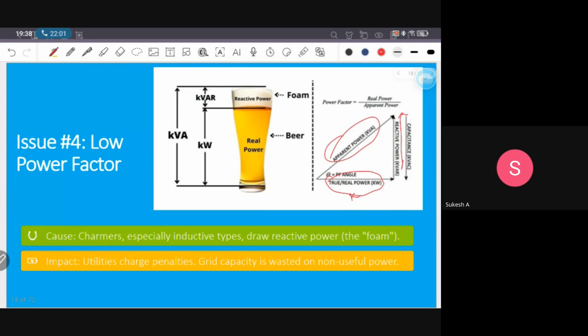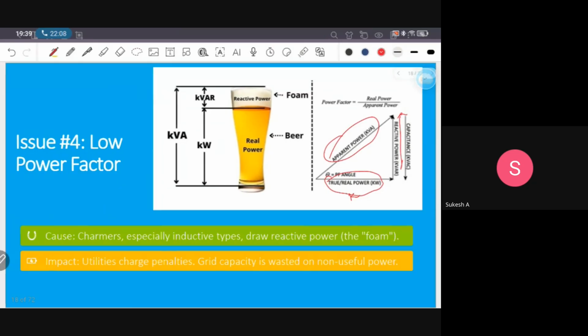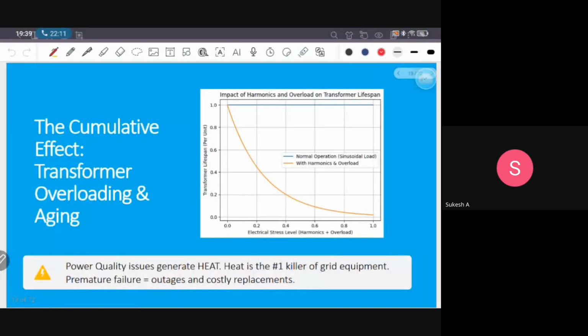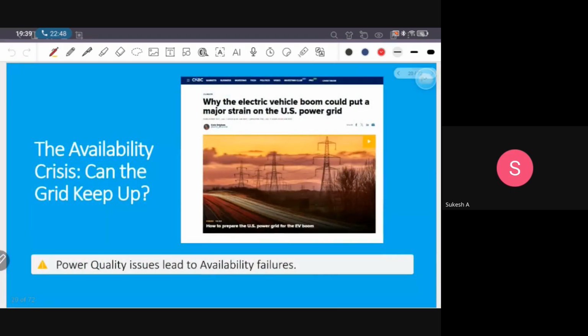And our EV loads and EV local loads are also drawing reactive power. So the cumulative effect is transformer overloading and aging. Here we can see the impact of harmonics on the transformer, and it is overloaded like this. So its lifespan is reduced like this. This graph is taken from, I forgot to add the reference. I will share the slides and add the references in them. It's a case study, and they plotted this graph smoothly showing lifespan reduction with harmonics in the transformer.